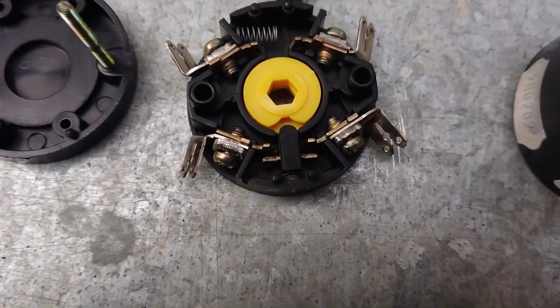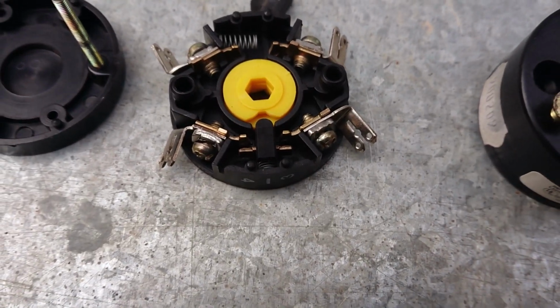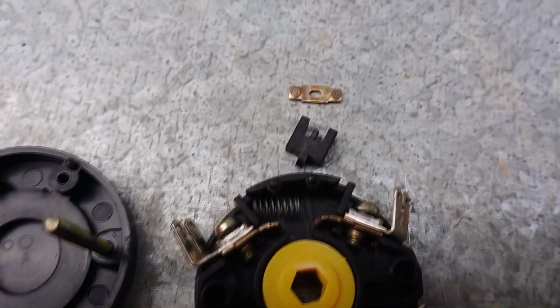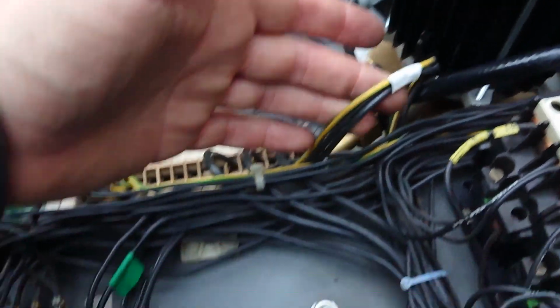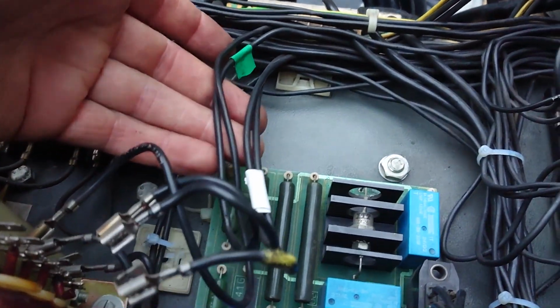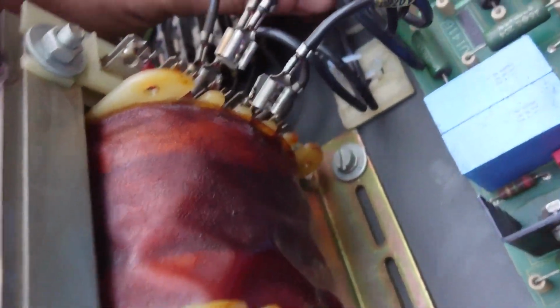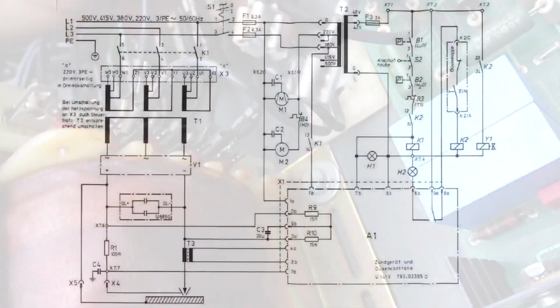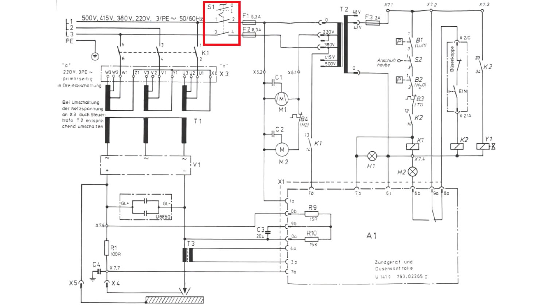That's my theory at least. So it must be something else then that connects to the output side of the switch, which I have marked here with white tape. And it leads to a tap on this transformer here. And as you can see in this circuit diagram, the switch via our blown fuse leads to the primary winding of the single-phase mains transformer. To be more precise, to the 0 and 380 volt taps.